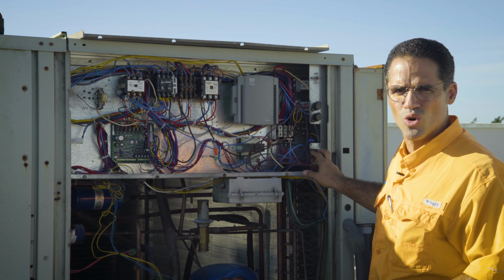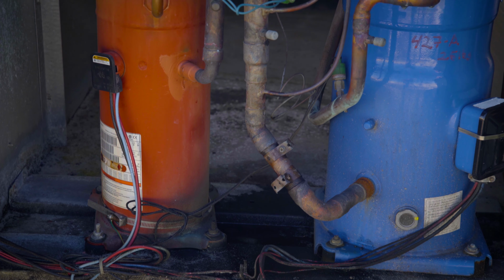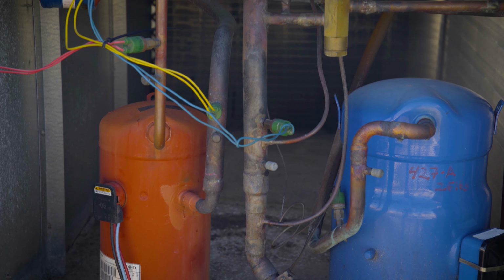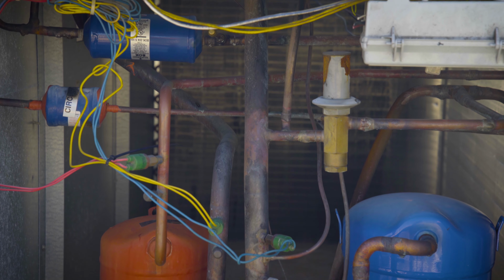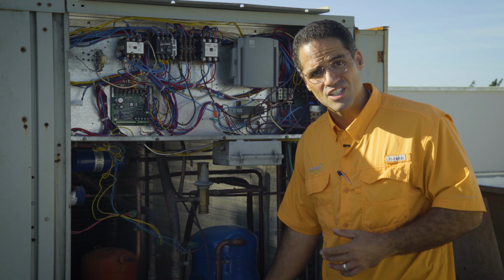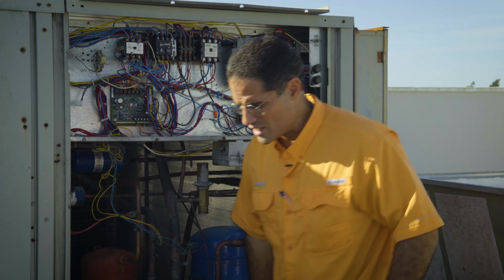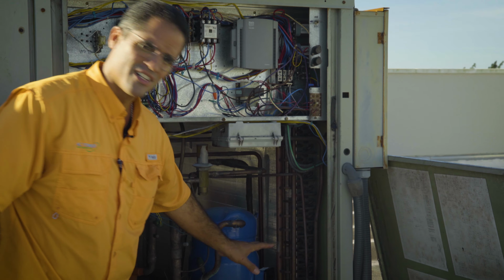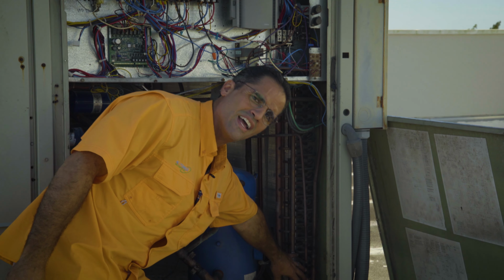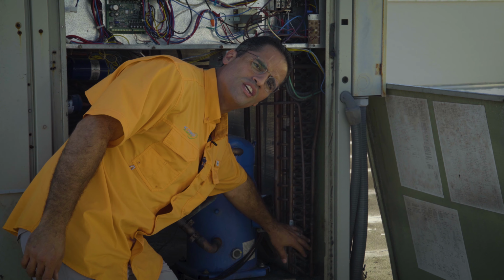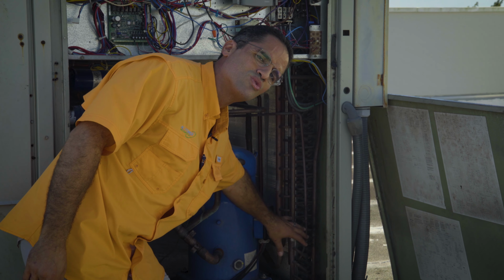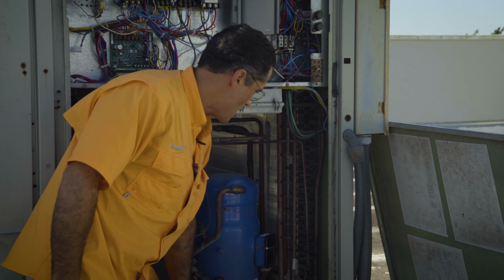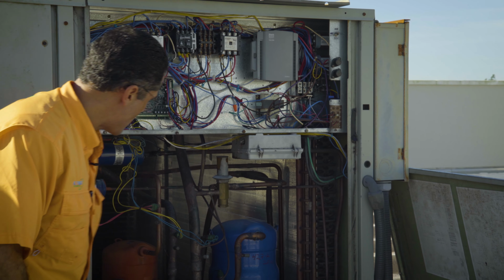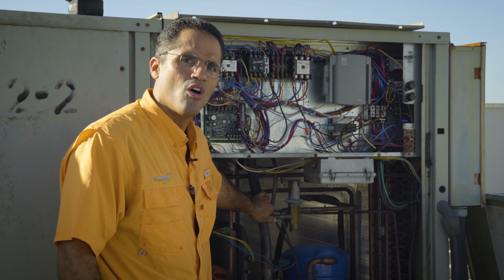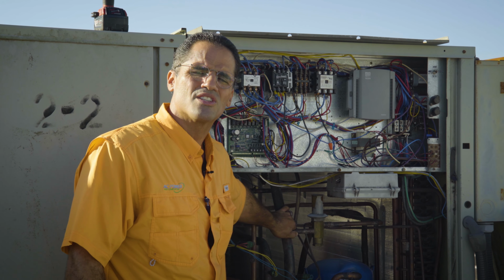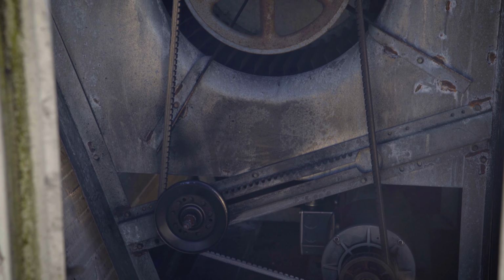However, that will be done shortly. On the refrigeration section, what we do when we do our maintenance is inspect all the refrigeration piping just to make sure that there are no oil leaks. We check the condenser coil section over here, and the main section that we always check is around the lower end, which is the liquid line side of the condenser coil here, because the majority of the time this is where leaks tend to happen more often. That's pretty much what we do when we cover the refrigeration section, verifying if there are any oil leaks or oil stains.